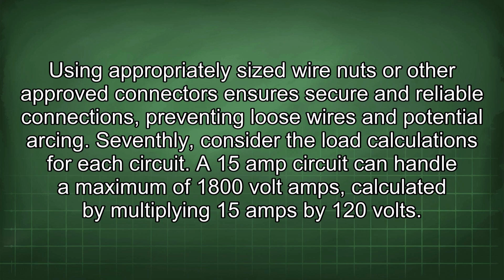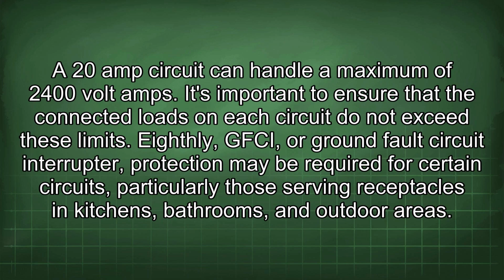Seventhly, consider the load calculations for each circuit. A 15 amp circuit can handle a maximum of 1800 volt amps, calculated by multiplying 15 amps by 120 volts. A 20 amp circuit can handle a maximum of 2400 volt amps. It's important to ensure that the connected loads on each circuit do not exceed these limits.